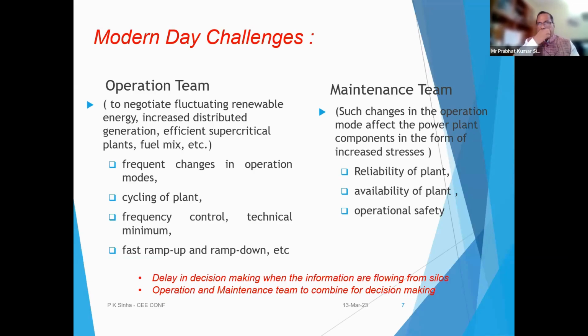That's the reason the operation teams at aging power plants are facing frequent changes in operation mode, cycling of the plant, frequency control, technical minimum, fast ramp up and ramp down. With respect to that, the maintenance team faces the challenge of not being able to match those requirements because of the deterioration in components, and the reliability, availability, and operational safety of the plant are all getting affected. Such challenges were not envisaged or planned earlier; rather, they are coming up as we grow.